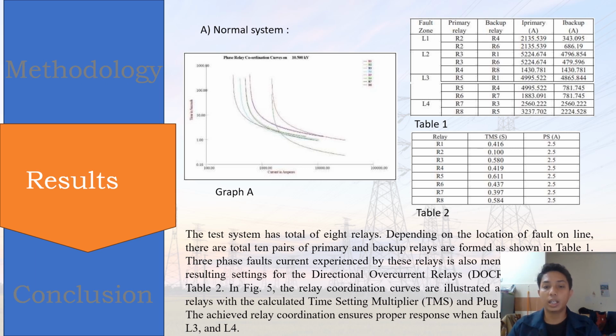The 3-phase fault current experienced by these relays is also shown, resulting in the settings for the directional overcurrent relay in Table 2 in figure 5. Here, as stated in the slide, the relay coordination curve illustrates the relays with a calculated time setting multiplier and plug setting multiplier, to achieve relay coordination and ensure proper response when a fault is at L3 and L4.